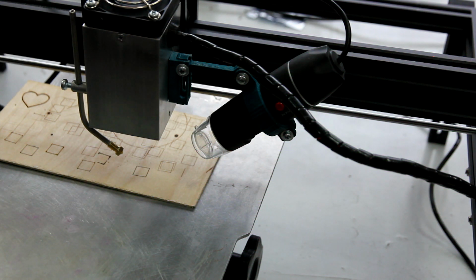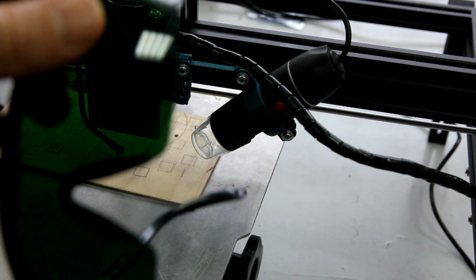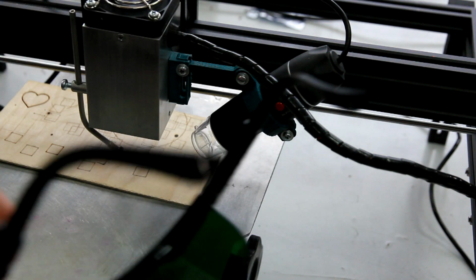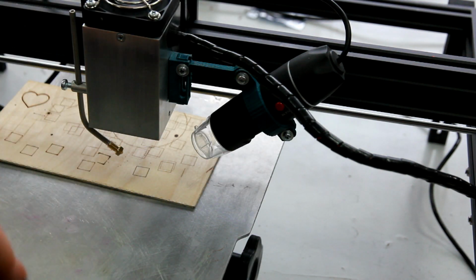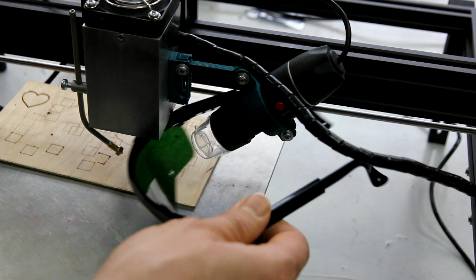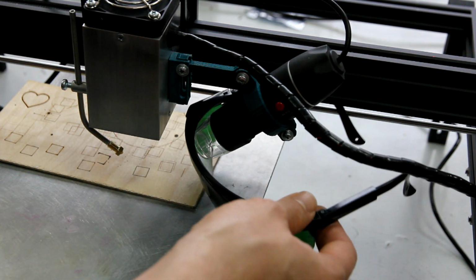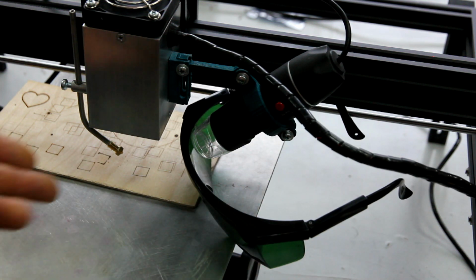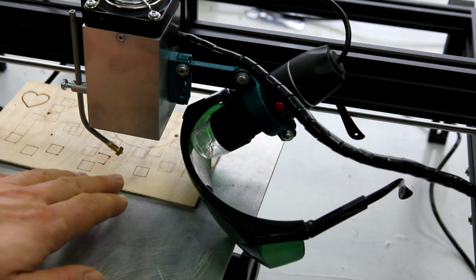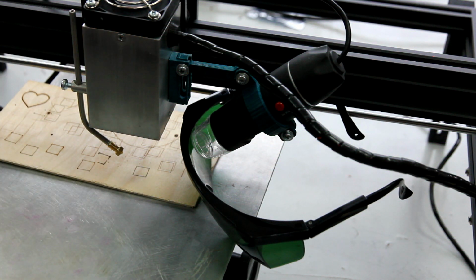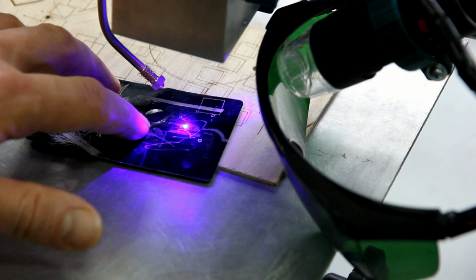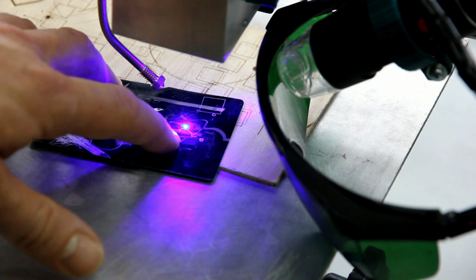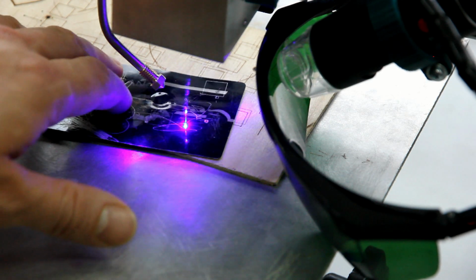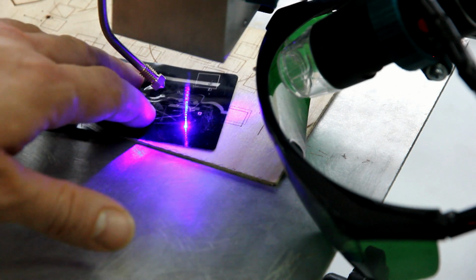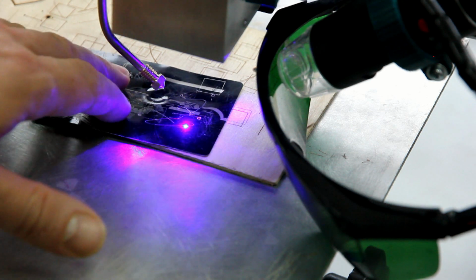Another nuance that you need to keep in mind is that you need a filter, because even on low focusing power, it's still too bright. So you need to put some filter, like a green or red filter, to be able to see the laser beam spot. Focusing power, and you see the spot here, so you can hear the noise. It's our life hack for how you can check that you're in focus.